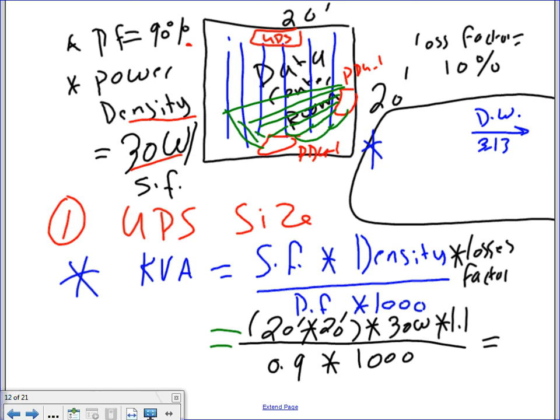So 20 times 20 times 30 times 1.1 divided by 0.9. Yeah, but in order to accommodate for the loss factor, you need this amount plus 10% extra. See what I mean? This is 1.1, guys. The 1 is for the system, the 0.1 is the extra. So how much? 14.6? 14.67 kVA. So I have a second. Yep, I got a second.